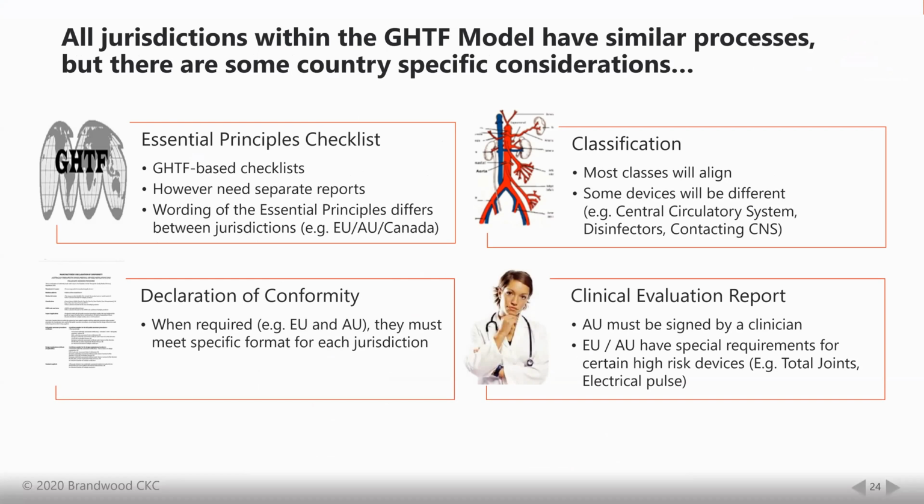Declaration of conformity, which is a document as part of your tech file. There is a European version and an Australian version, and then your clinical evidence. So there are a few differences between Australia and Europe. You can definitely cover your jurisdictions in the one tech file, as there is so much overlap, but it's really important to keep in mind that there are differences among them.